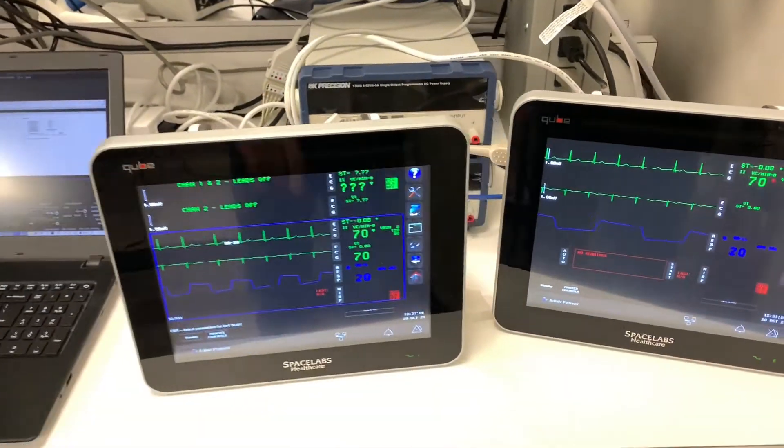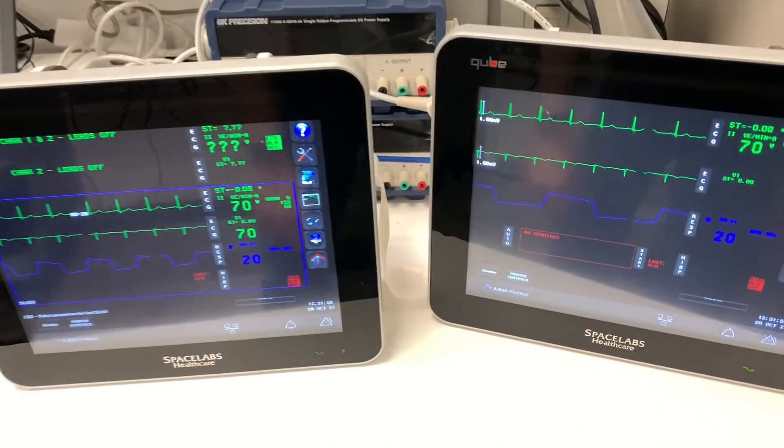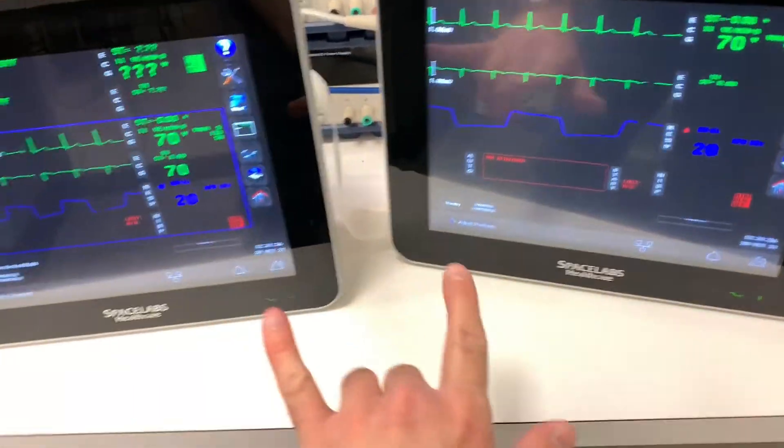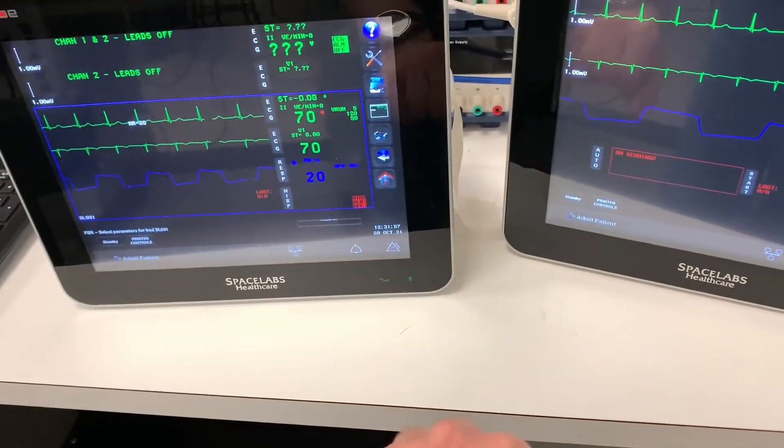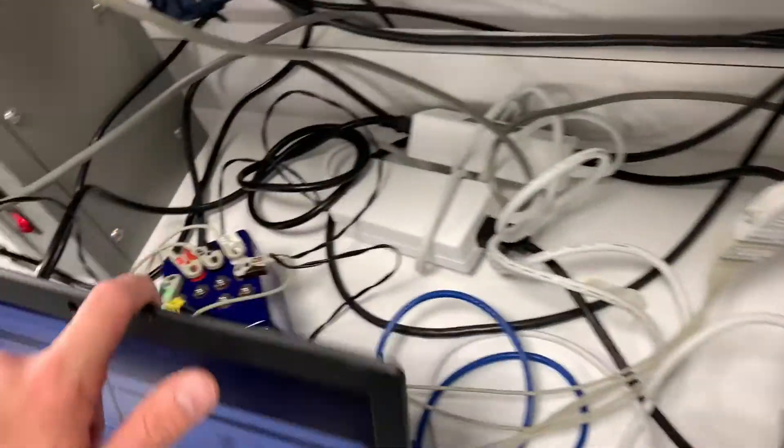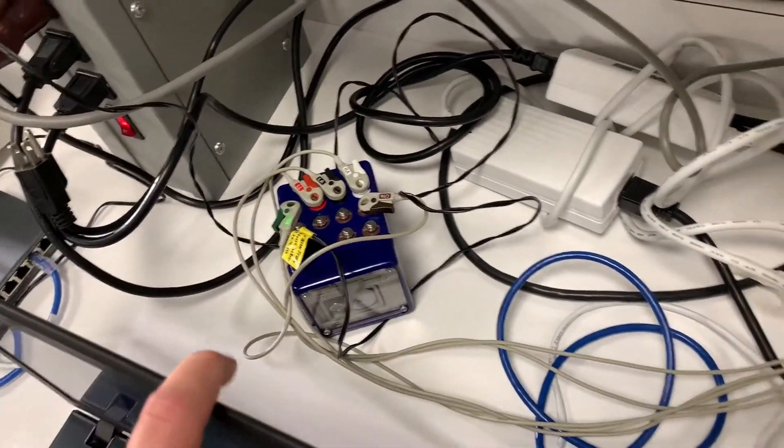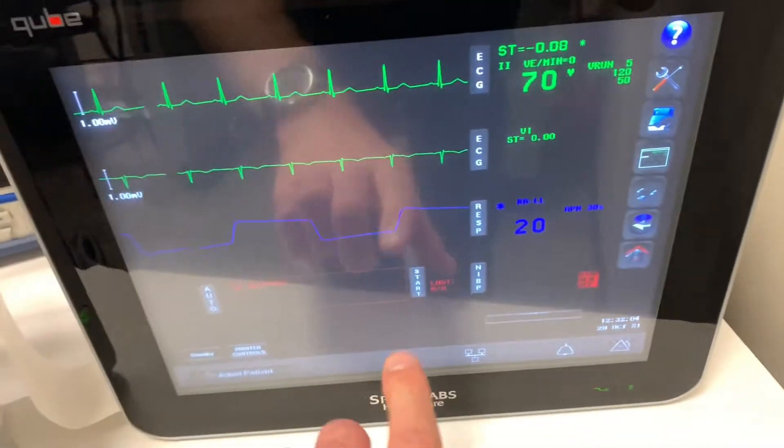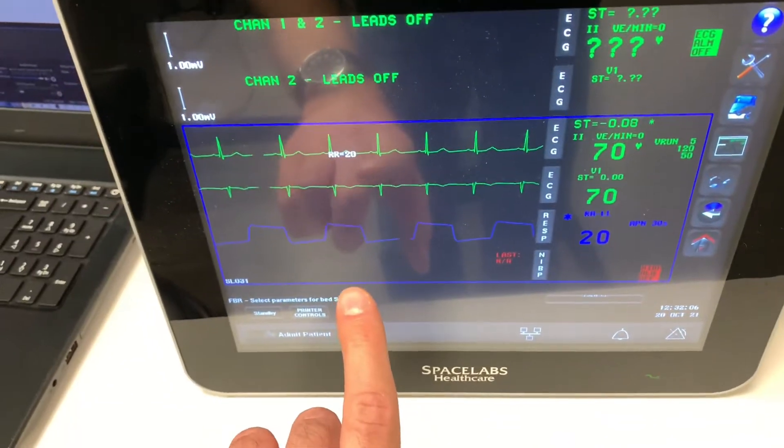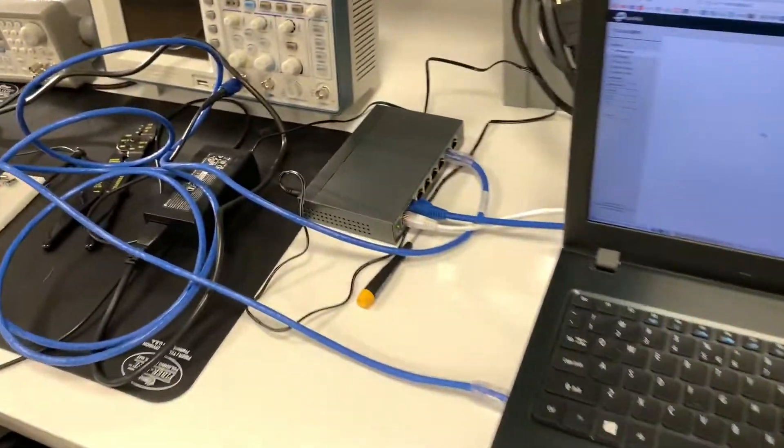These ECGs are set up just like the last video, so they both have static IP addresses. This one is hooked up to the simulator back here. That's pulling trend information from that and sending it over to this one through the switch over here.